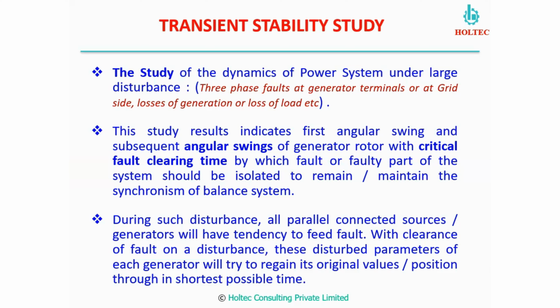Now, what happens when we apply these kinds of faults? There will be a fast change in the angular swing of the rotor. Suppose, for our understanding, one generator is operating. When a fault happens in any of the motors, or a fault happens in the grid with which this generator is running in parallel, this generator will start feeding fault current. A huge amount of load is then exerted on the rotor, which causes the rotor to slow down. If it is a throw of loads, then the generator speed will go high. But if it is a fault, then the generator speed will go down.